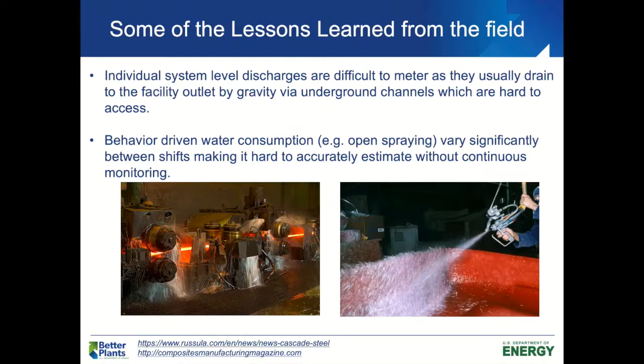The last point I have is with respect to behavior-driven water consumption. For example, in the case of open spraying, it could significantly change with shifts, because it's totally dependent on the people using it. To accurately estimate it over a period of time, you need to data log it, capturing it across shifts and over multiple days so you get a good average. A single snapshot measurement is not a good measure of behavior-driven water consumption.